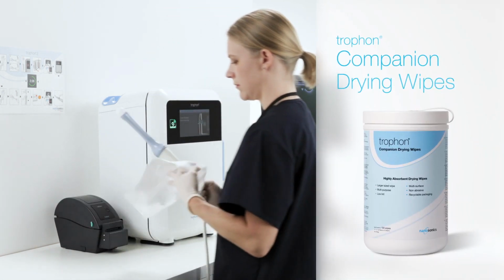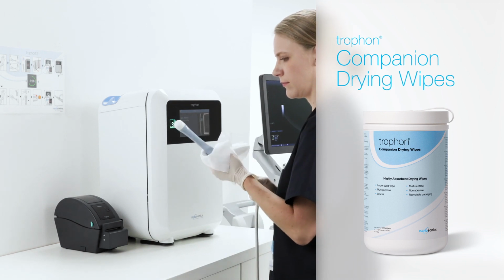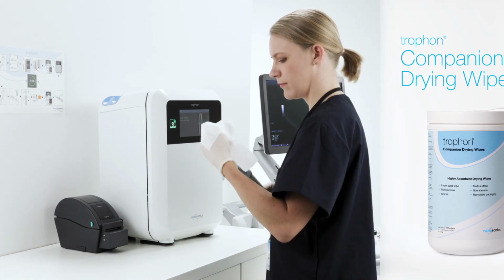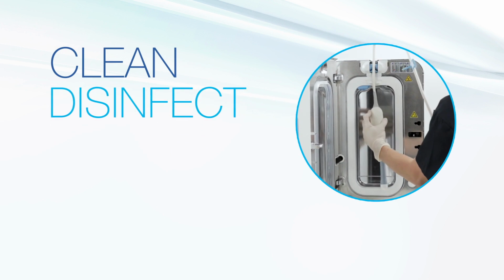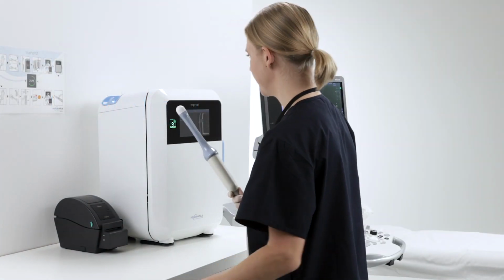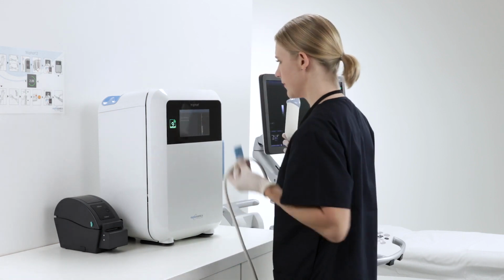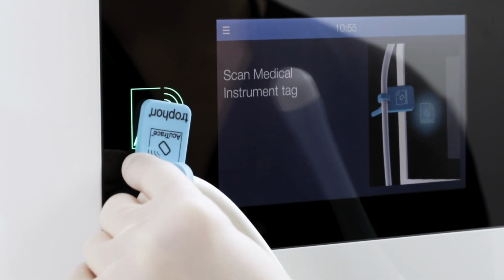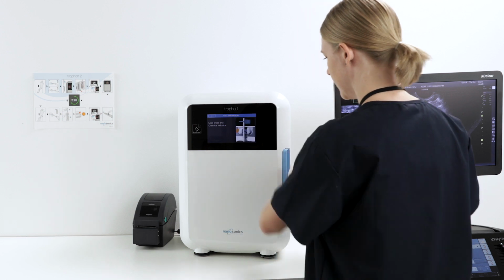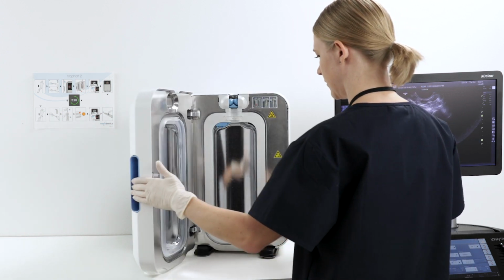Use a trophon companion drying wipe to ensure the probe is completely dry. Now your probe is clean and dry. Scan the medical instrument tag against the Acu Trace reader until a beep sounds. Load the probe into your trophon2.